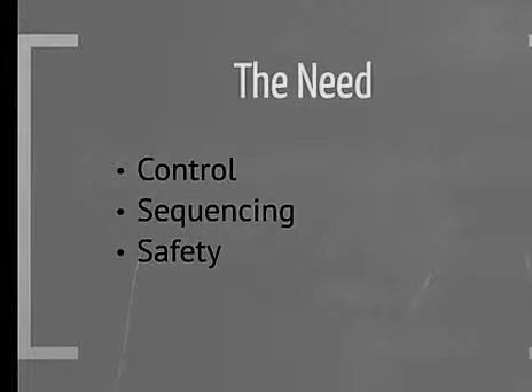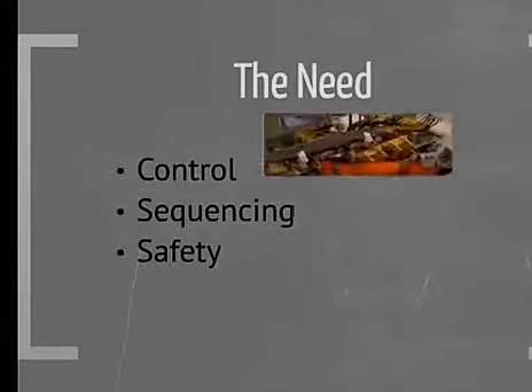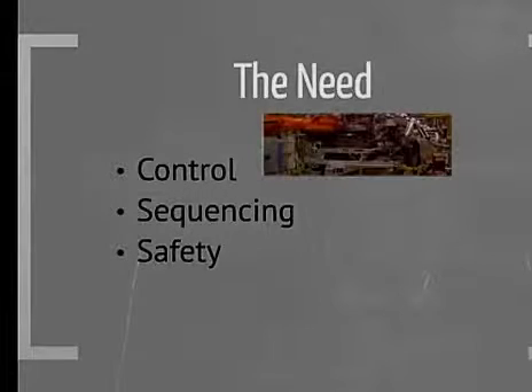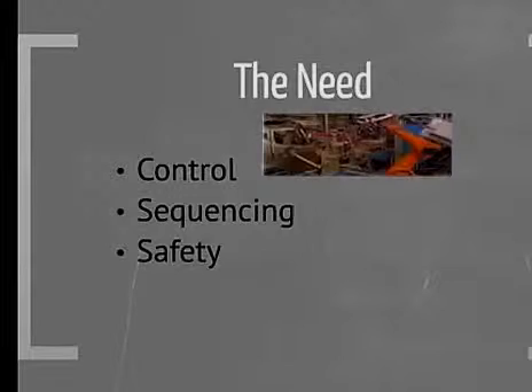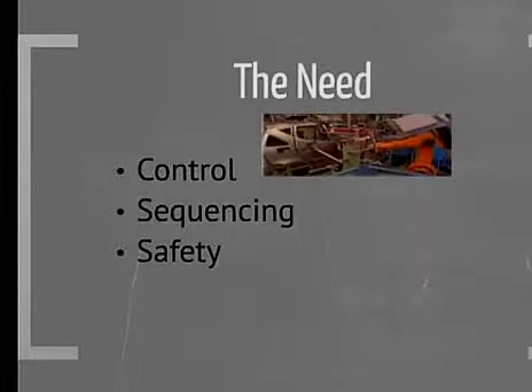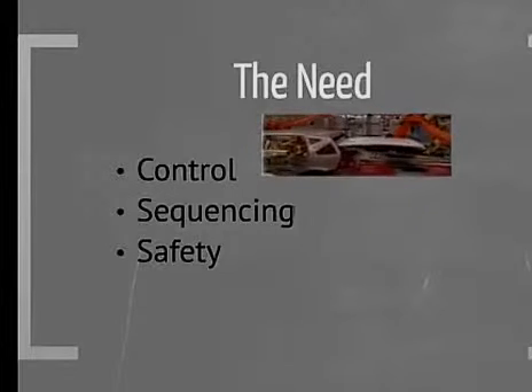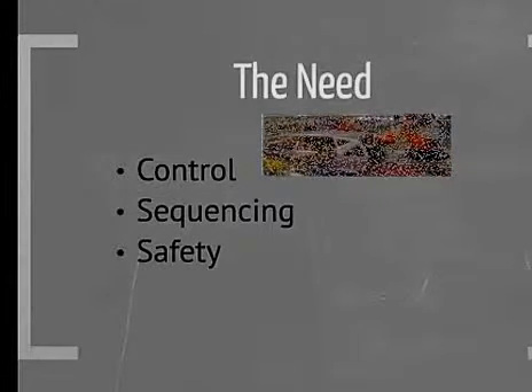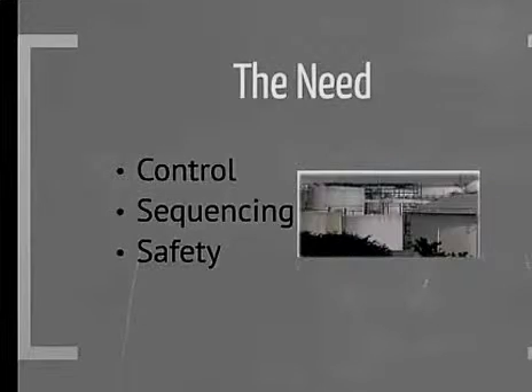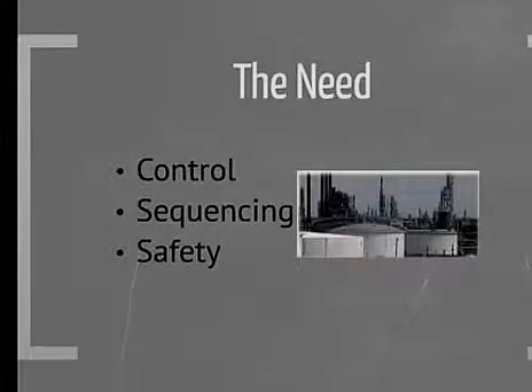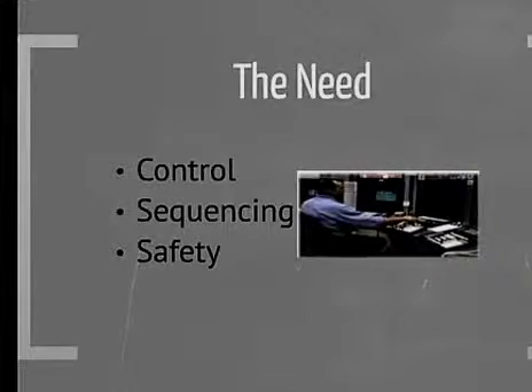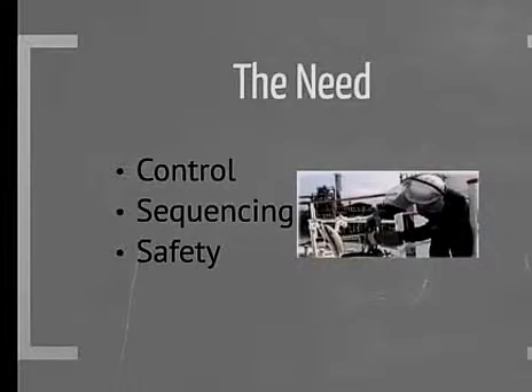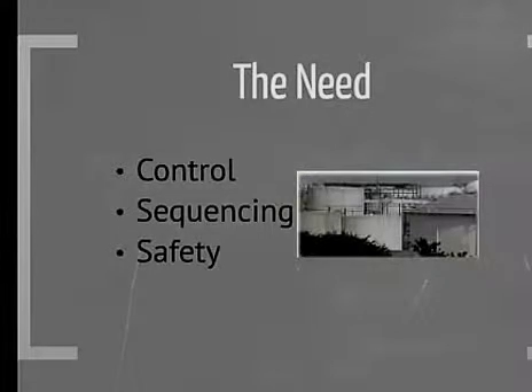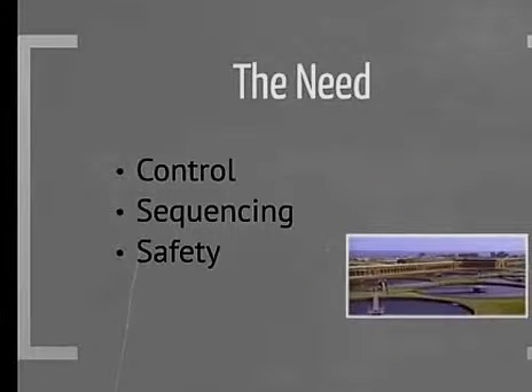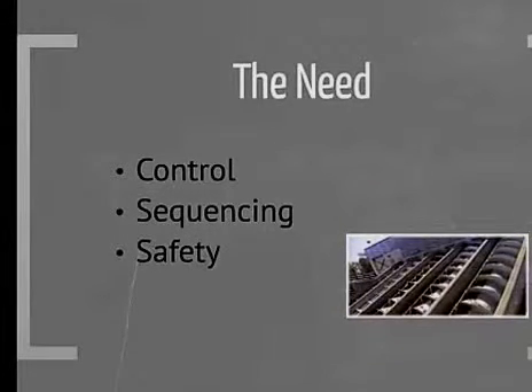PLCs are well adapted to a range of automation tasks. These are typically industrial processes and manufacturing, where the cost of developing and maintaining the automation system is high relative to the total cost of the automation, and where changes to the system would be expected during its operational life. PLCs contain input and output devices compatible with industrial pilot devices and controls. Little electrical design is required, and the design problem centers on expressing the desired sequence of operations. PLC applications are typically highly customized systems, so the cost of a packaged PLC is low compared to the cost of a specific custom-built controller design.